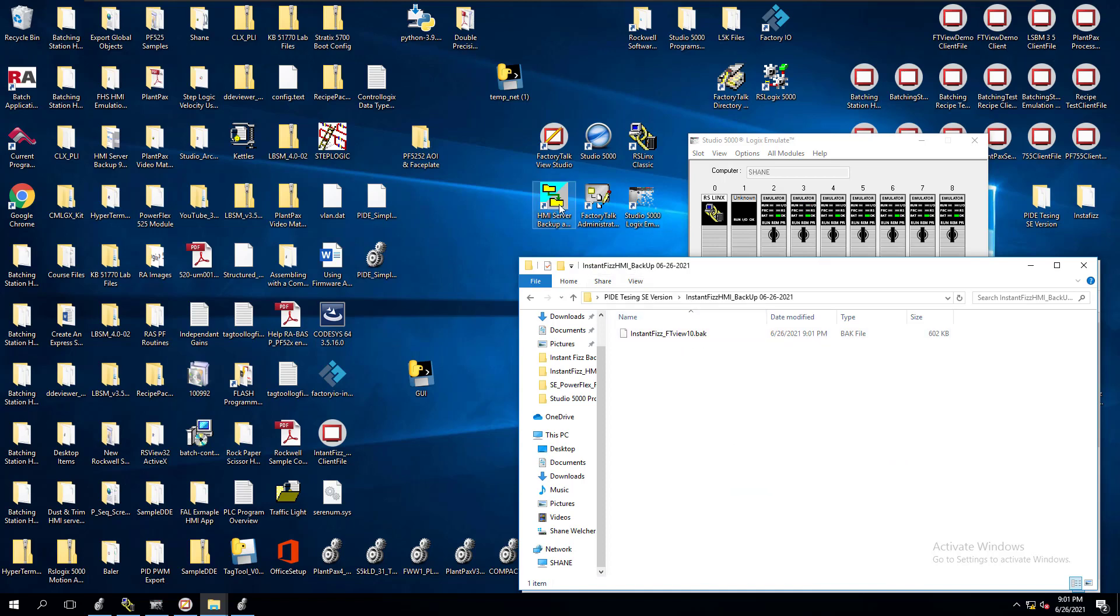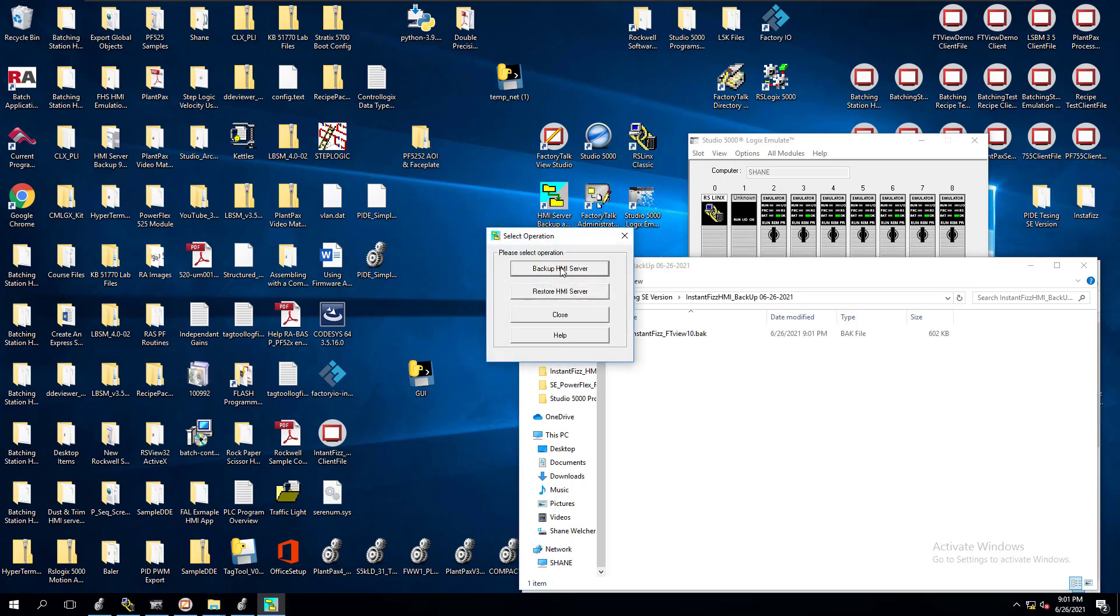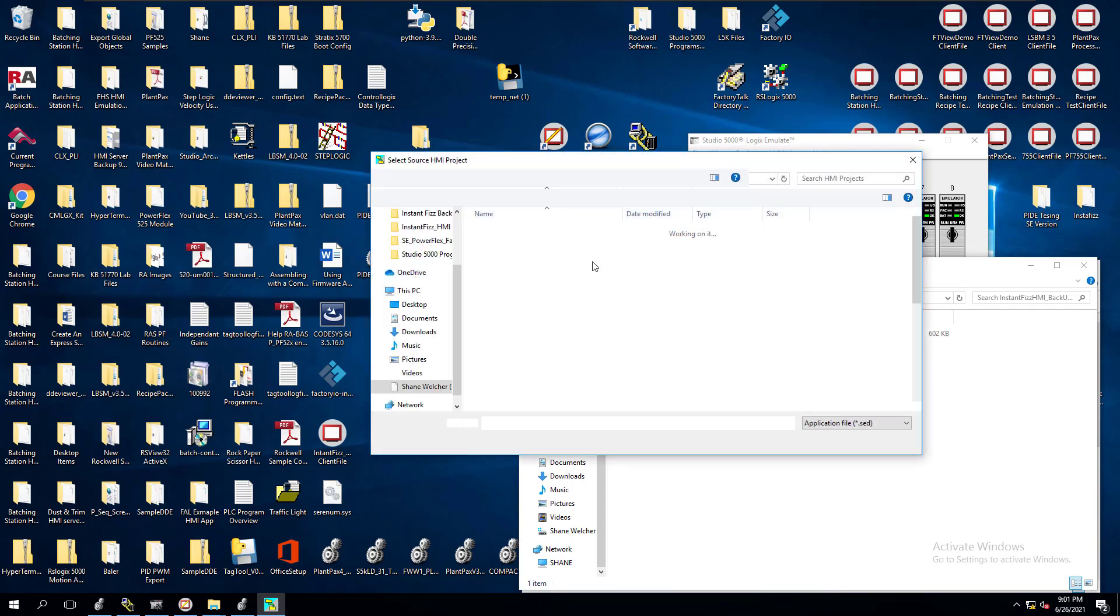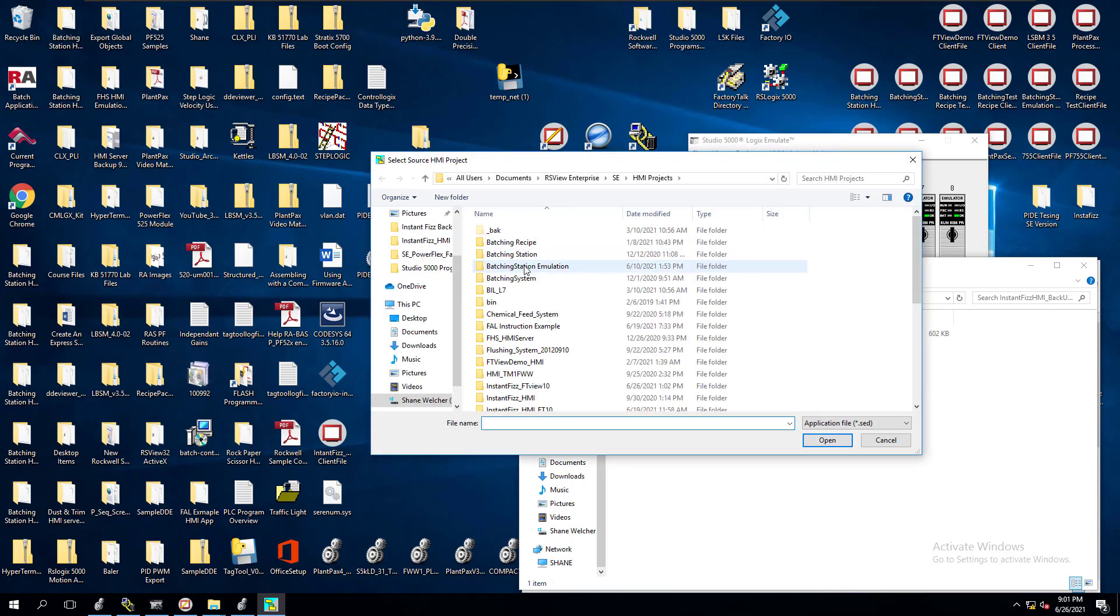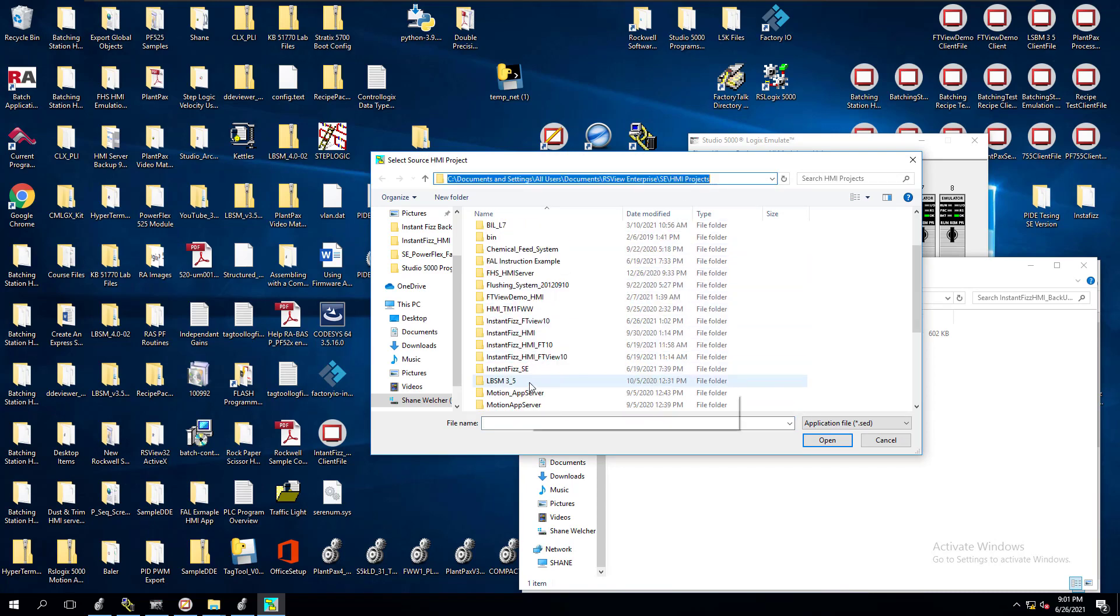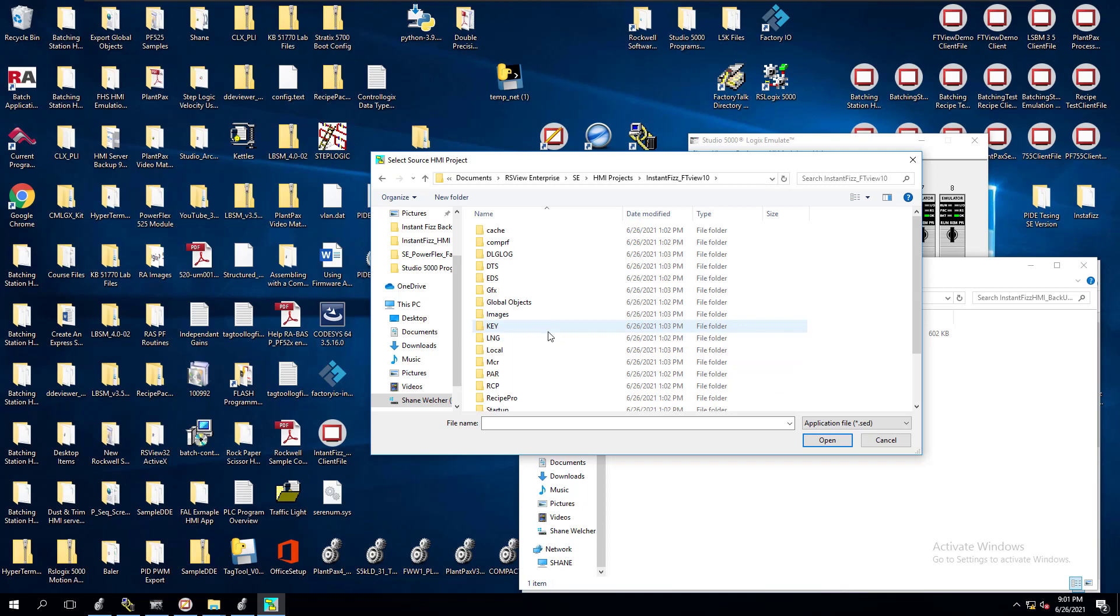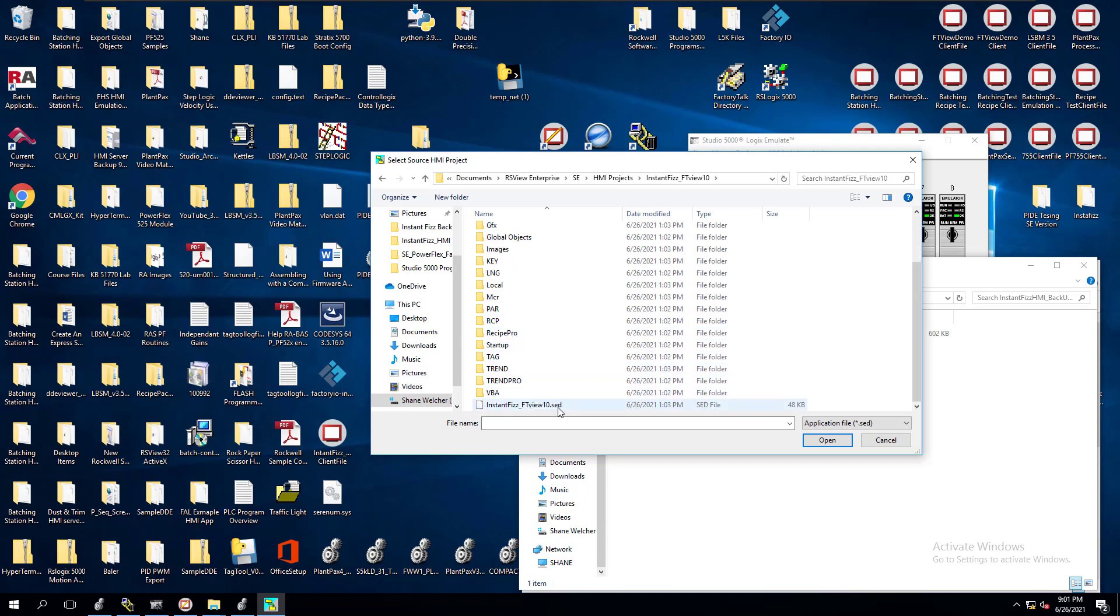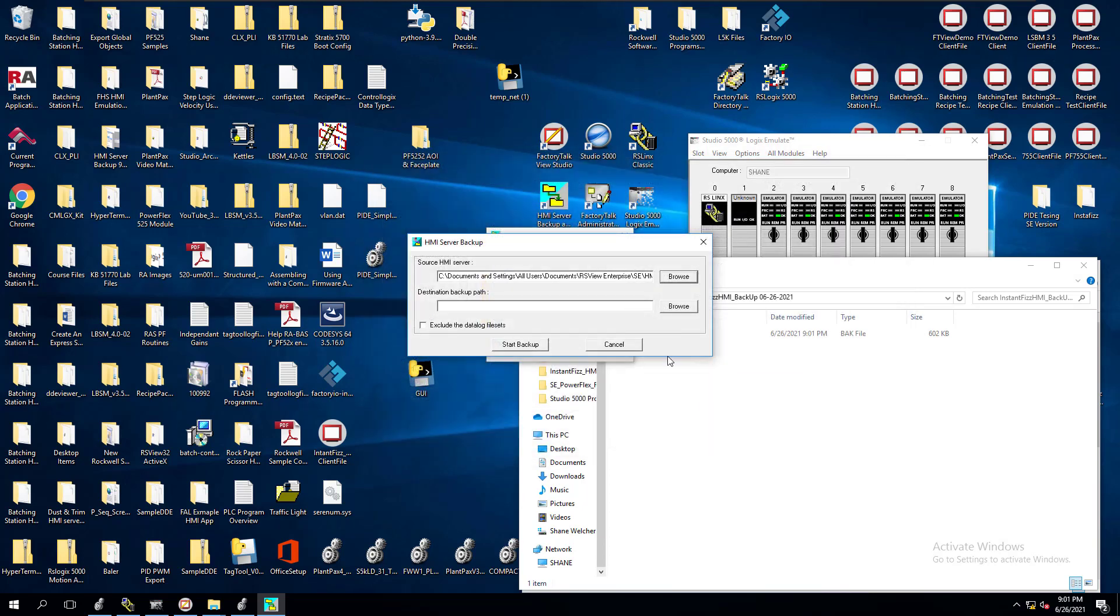So now we need to open up the HMI server backup and restore. We're going to hit backup, we're going to pick our application. It's going to automatically open up to the file location, and we're going to go down to the file location that we have. This is the one we made today. So I'm looking at the date here. I'm going to open that one up. I'm going to go down to the .sed file, and I'm going to pick that, and I'm going to hit open.